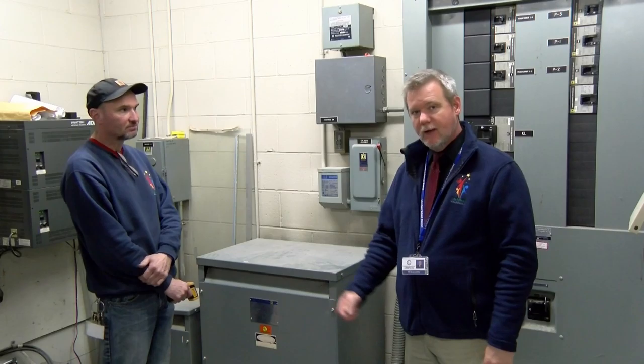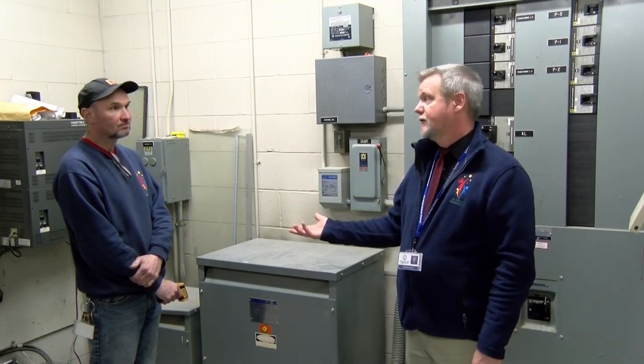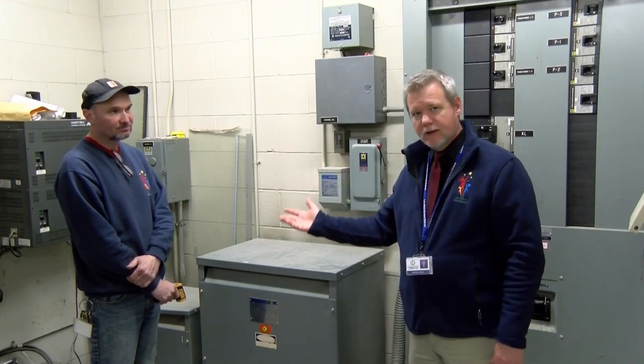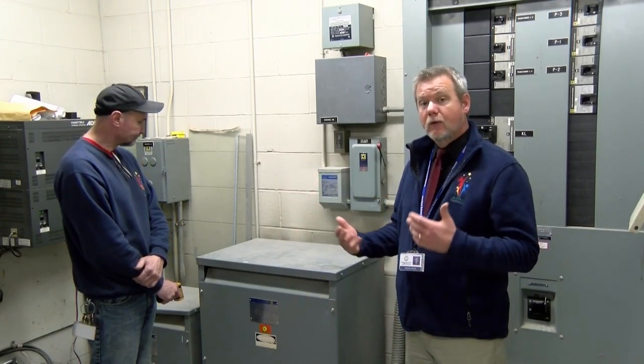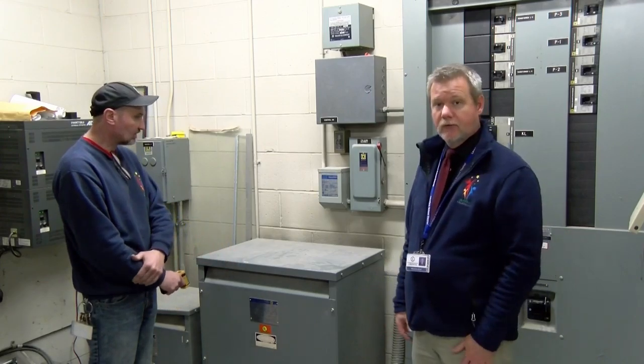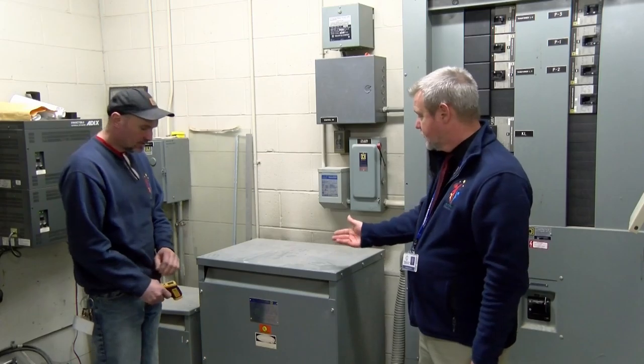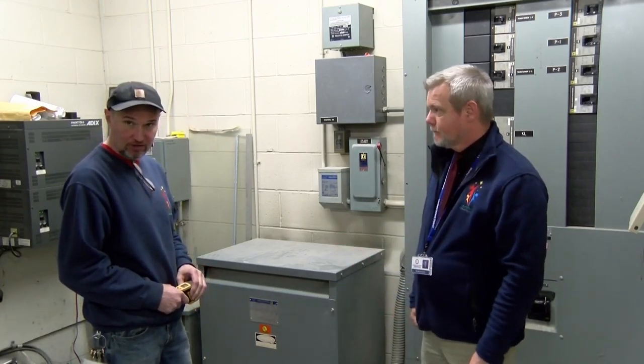It did happen in the summer. And that was actually a 1970s era component. So, you know, it wasn't something that goes back to the 50s or earlier. So we're facing a similar problem here at the middle school. So upgrading this is important. These units get very hot. Dave, you want to just explain? Yeah, so this is our transformer, 480 volts.